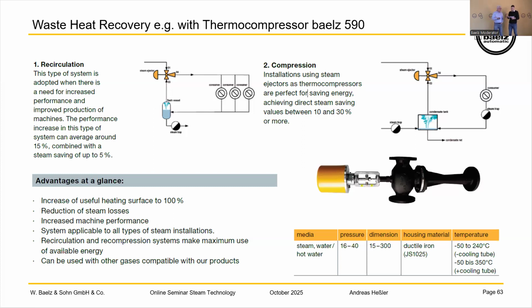Yeah, this was pretty much the second part of the question. So is there a rule of thumb for the ratio between motive steam pressure and low steam pressure? So the steam you want to use for your application? Very hard. When you have 1 bar to 3 bar, that is one ratio. When you have 10 bar to 15 bar, it's only 5 bar. So I would say very hard to say right now. We have to check. It's better you come to us and say, I want to have this and this, and then we say it works, or it could not work, and then we have to make some decision.